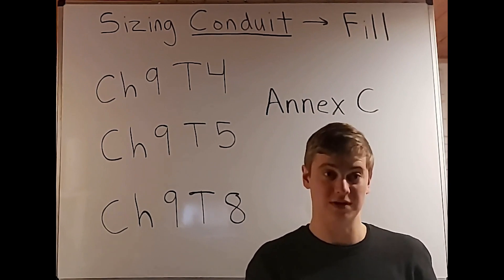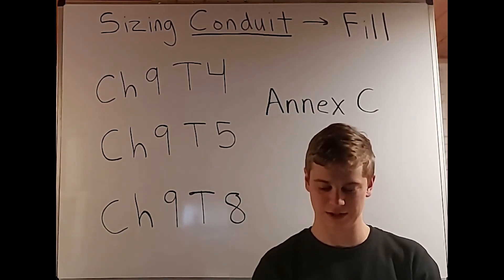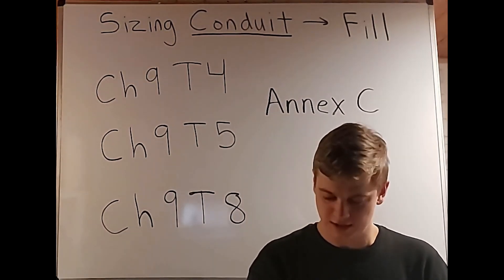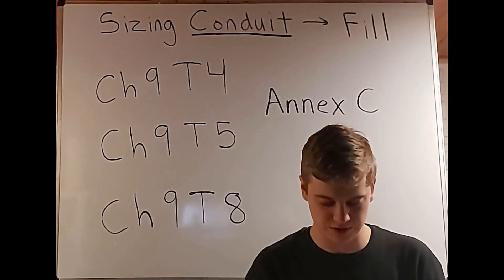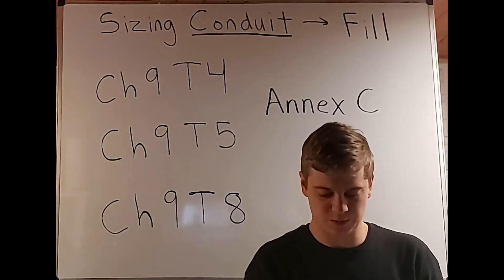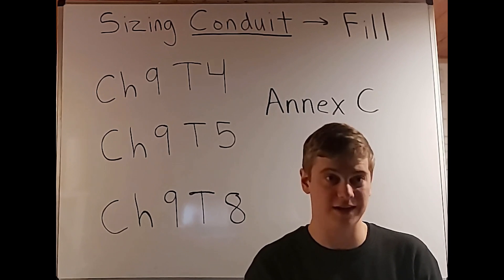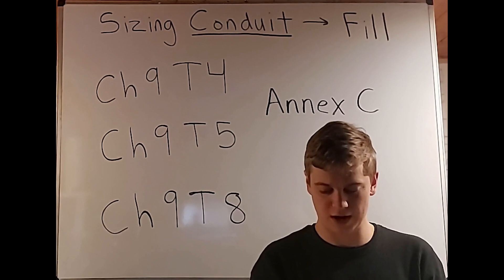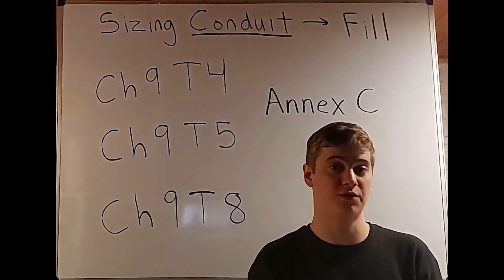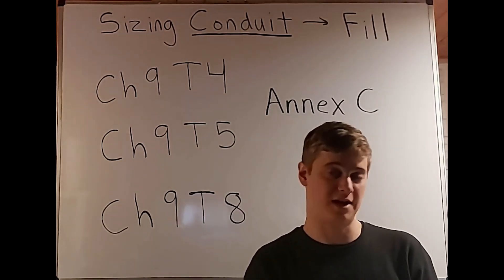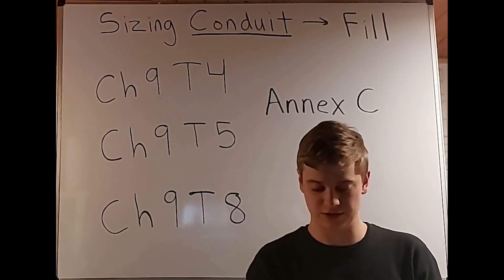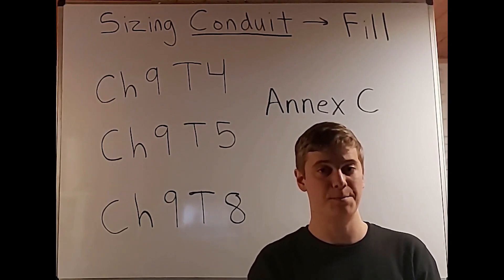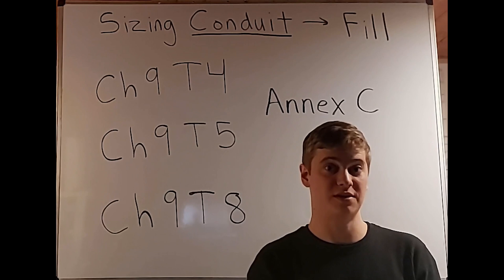I'm going to read from the codebook now, but I'm not going to read the entire thing because of plagiarism. When we go to Chapter 9 in the codebook, we see Table 1, and that is the percentage of the cross-section of conduit and tubing for conductors and cables. On the left side, we have the number of conductors and/or cables. If we have one conductor or cable, we have a demand factor of 53%, so we're going to be multiplying the area by 0.53.